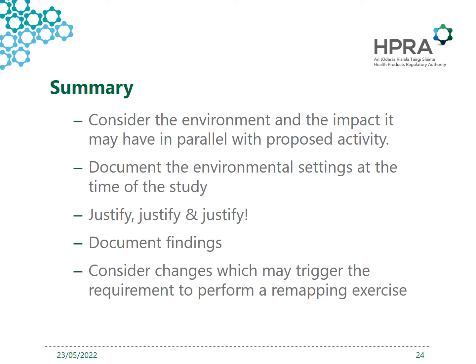Then document the environmental settings at the time of the study. It's important to show the settings and what was in place during the study is reflective of normal operating conditions - things like the set point of any equipment used, the alarm limits, or the external temperature on the day should be documented.